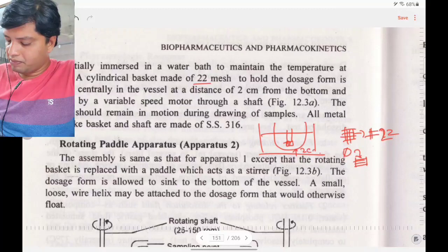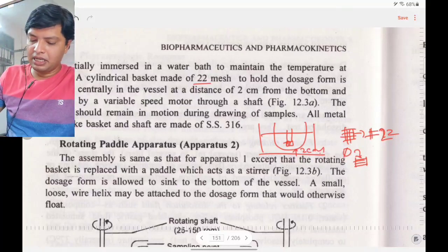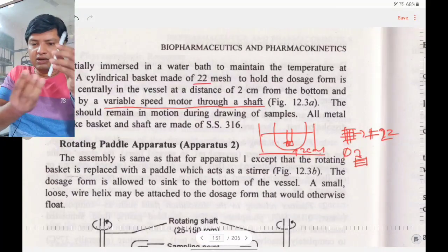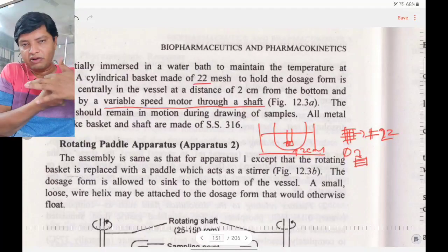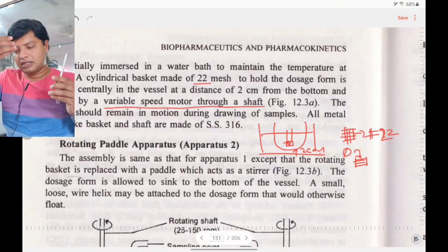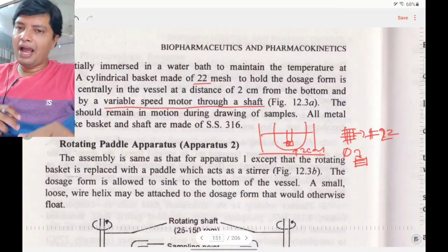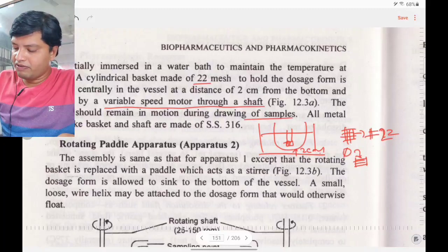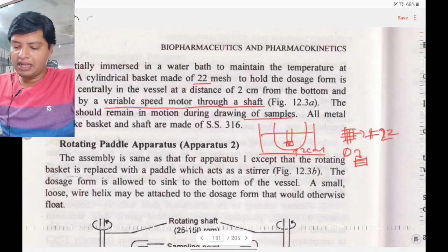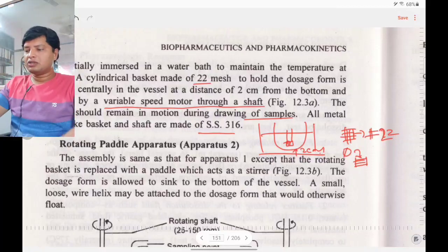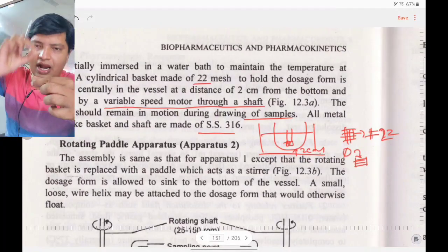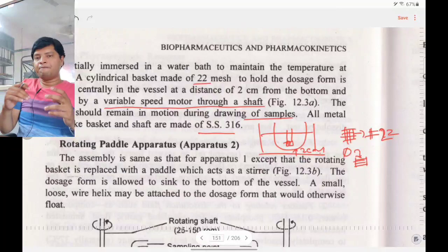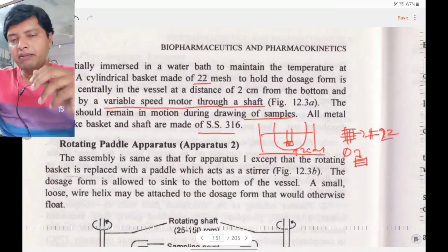The basket remains in motion during the drawing of samples. All metal parts, including the basket and shaft, are made of stainless steel. The dosage form is placed in the mesh basket, which rotates inside the hemispherical beaker partially immersed in the water bath maintained at body temperature.